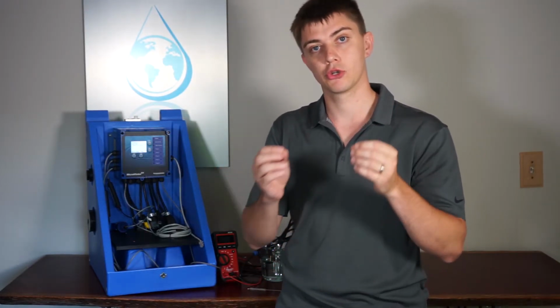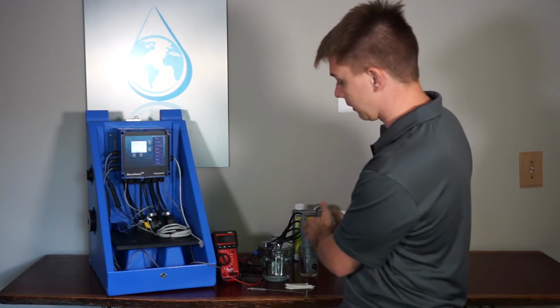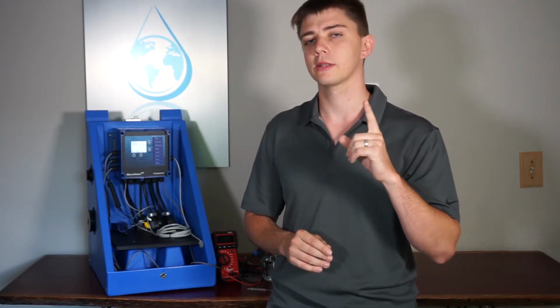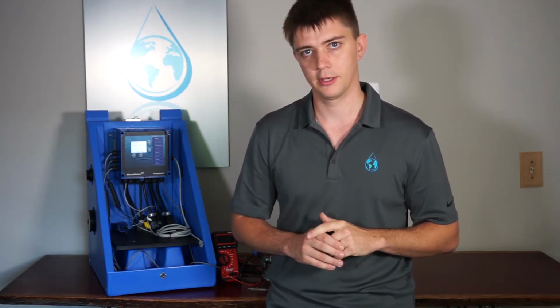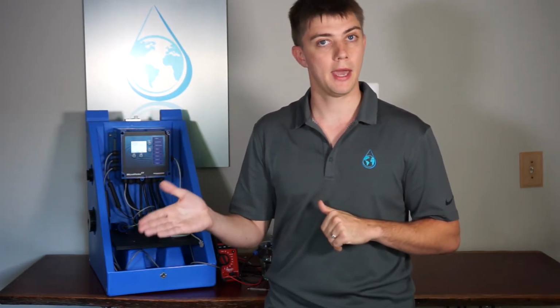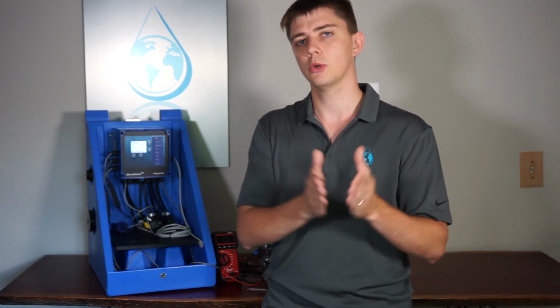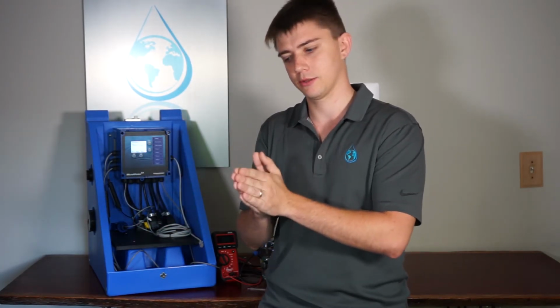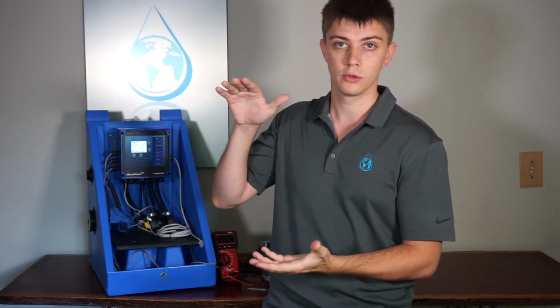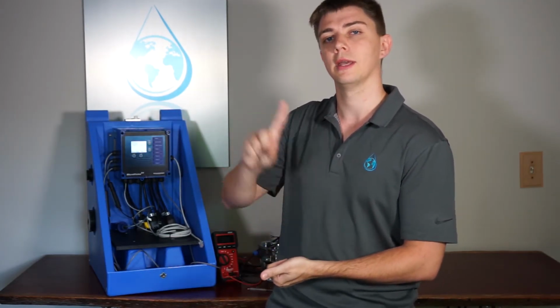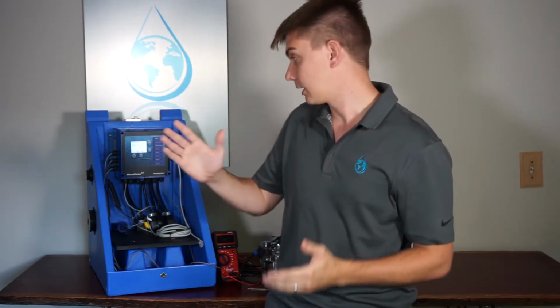The other thing I want to ensure that you do anytime you're feeding inhibitor off of a PTSA probe is use a limit timer. If your probe reading goes bad for whatever reason, you want to ensure that you have a limit timer set so that you don't suck a full drum of chemical and dump it into the tower. Limit timers are going to basically time every single time that relay turns on and ensure it doesn't stay on for longer than a certain amount of time.